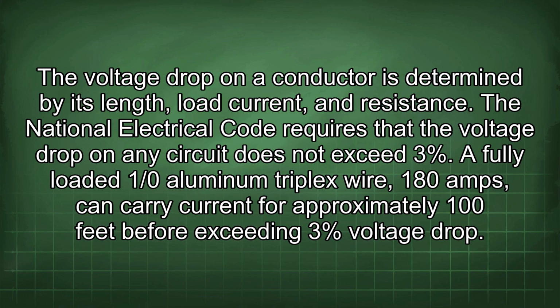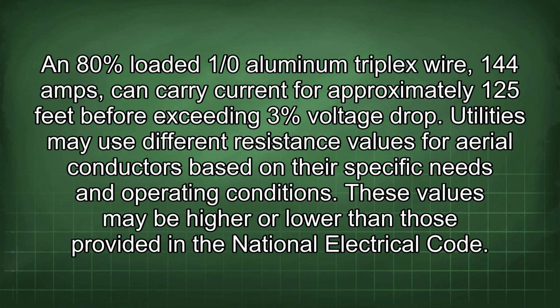The National Electrical Code requires that the voltage drop on any circuit does not exceed 3%. A fully loaded 1/0 aluminum triplex wire, 180 amps, can carry current for approximately 100 feet before exceeding 3% voltage drop. An 80% loaded 1/0 aluminum triplex wire, 144 amps, can carry current for approximately 125 feet before exceeding 3% voltage drop. Utilities may use different resistance values for aerial conductors based on their specific needs and operating conditions. These values may be higher or lower than those provided in the National Electrical Code.